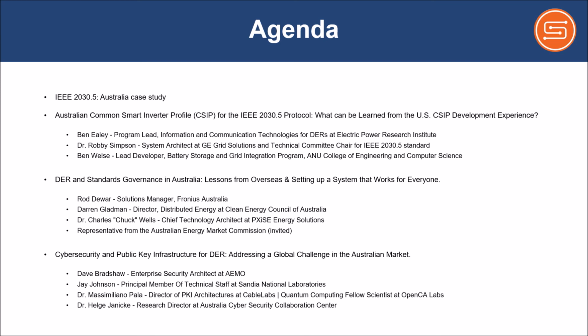Now, as it turns out, these protocols in 1547 serve different purposes. SunSpec Modbus works on the equipment for local plant equipment. DNP3 is very popular for substation automation. And then IEEE 2030.5 seems to hit that sweet spot for DER system to grid operator integration. That's what California has picked out as the default for the vast majority of their systems - 2030.5, for the reason Robby mentioned, that you have a lot of customer-sited equipment and you need a way to communicate at scale.